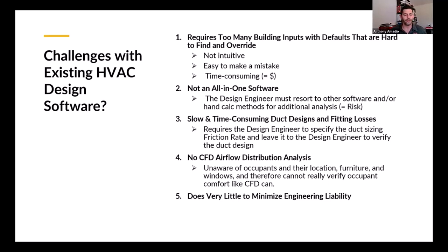So what are a lot of people doing? They're just drawing lines in AutoCAD or even Revit and just using a friction rate. Do they go back and validate it? Do they go back and check their fittings? Do they have time to do it? They probably don't. So many folks are dealing with a ductulator and just running with it, and usually it doesn't lead to a balanced design. And if you can't get the right airflow to the space, going to that next level and meeting Standard 55 is going to be even more challenging.